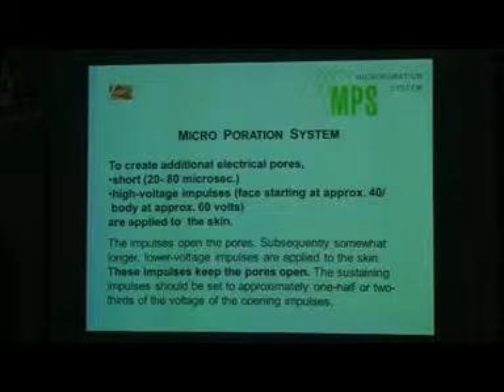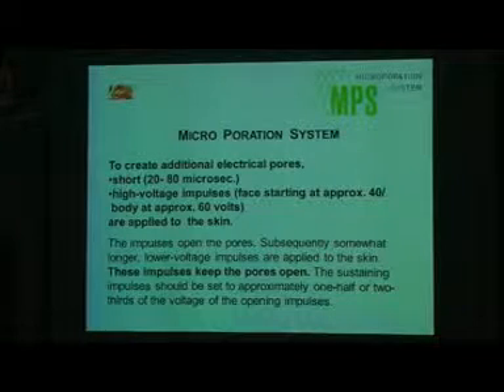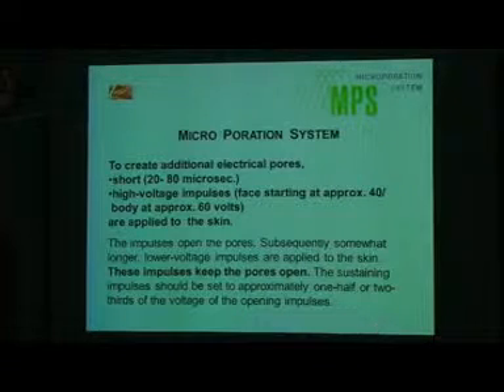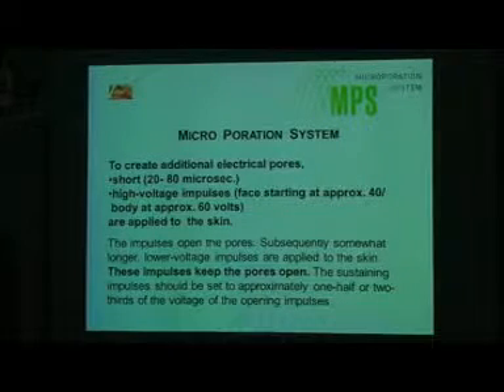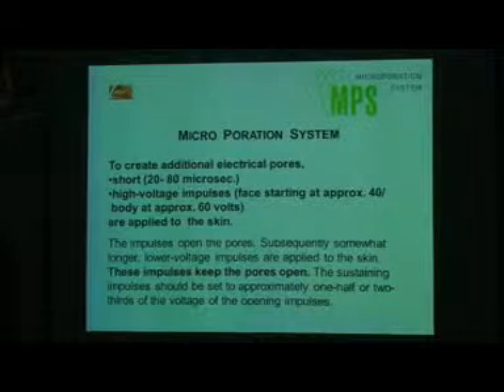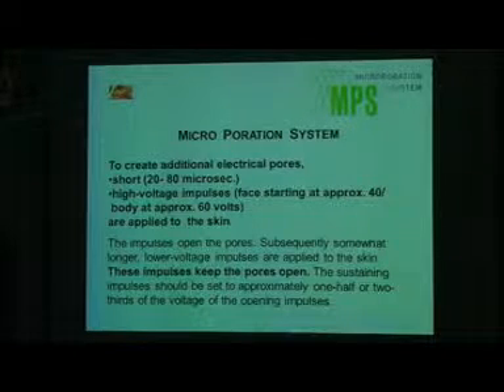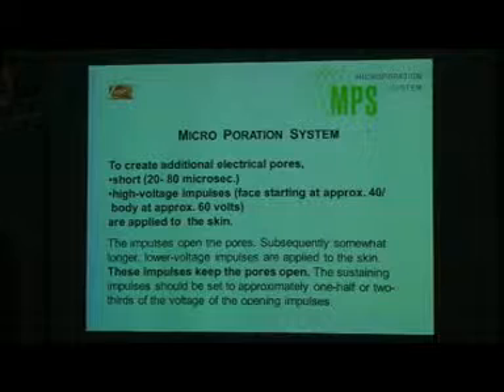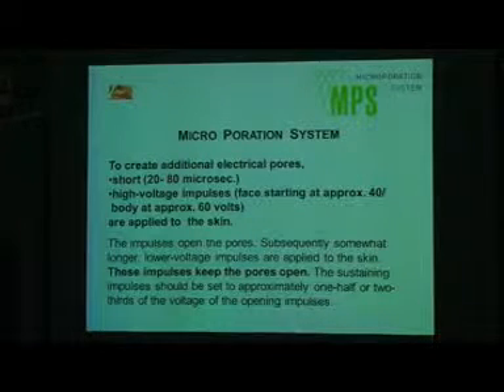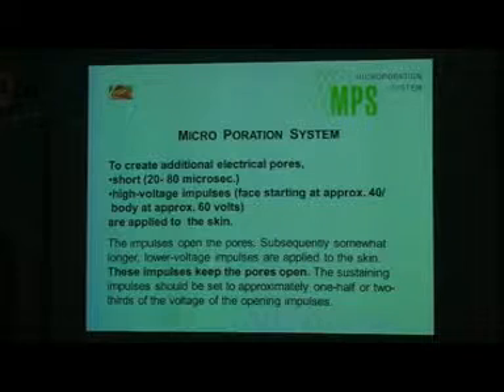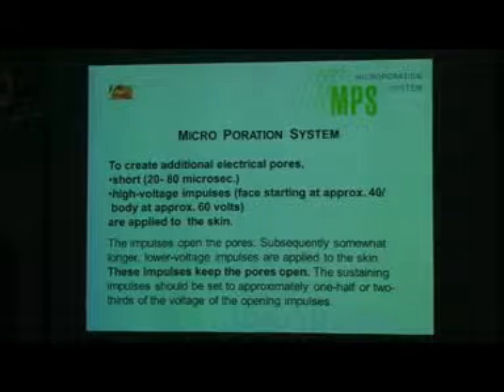So with this machine, we open the pores and subsequently apply somewhat longer voltage impulses to the skin to keep these pores open. Because this was a problem until, let me say, 4 or 5 years ago. The opening of these additional pores is not so difficult, but to keep them open over a certain time is the difficulty. And now, with these so-called keep-the-pores-open impulses, we can keep them really open over minutes, and this is very important.